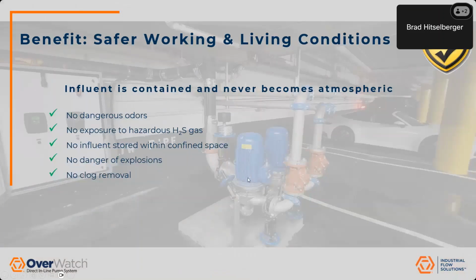So you can see this one is actually in a parking garage. So these things can be above grade. It just all depends on where that gravity invert is coming in. It's not ever going to be like a vacuum style pump or a suction lift pump. It's going to have to sit below that gravity invert, but wherever that gravity invert's coming in is where we're mounting right up to it. So you can see their control panel is mounted back there in the background as well, but this is actually in a parking garage too. So this just shows you how this thing works and how you can see that it contains all that influent, and so there's no odors at all, which is great.